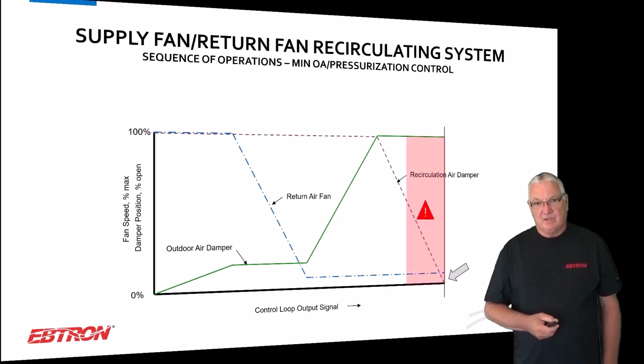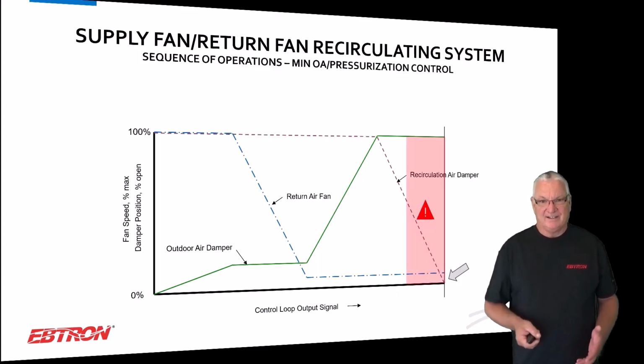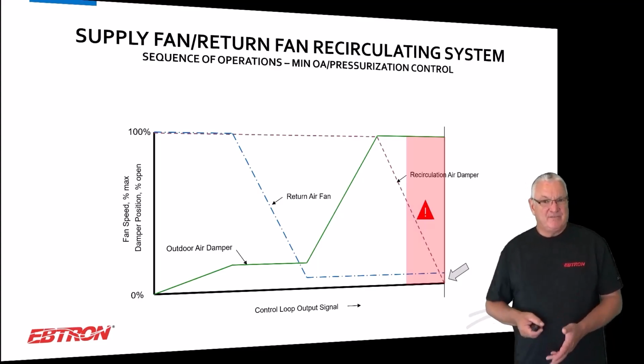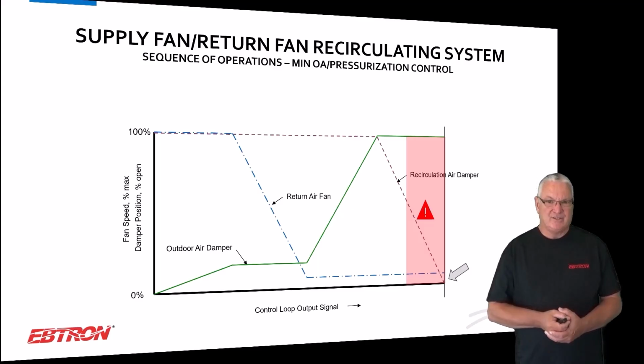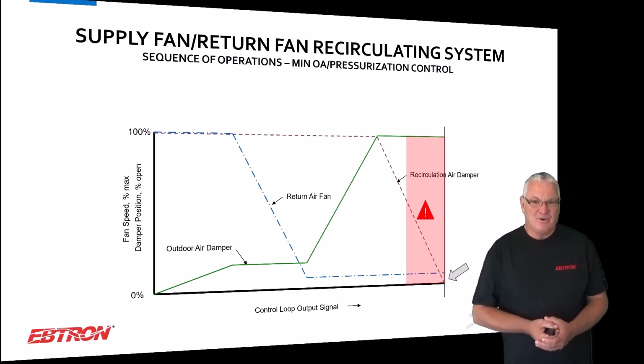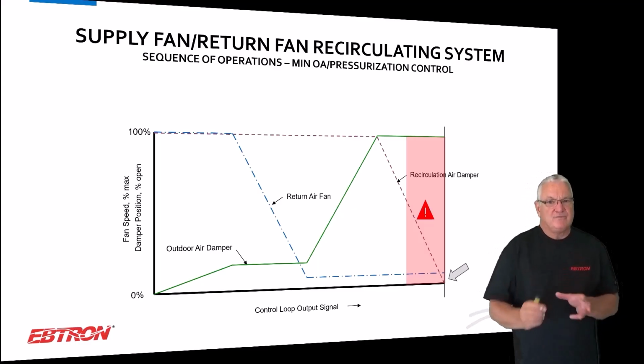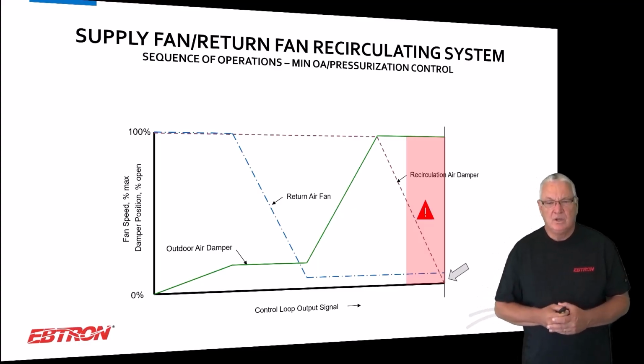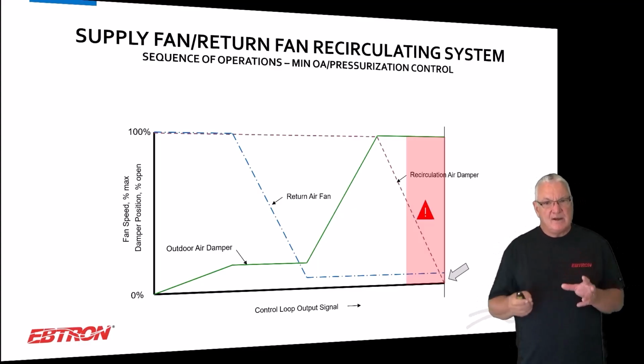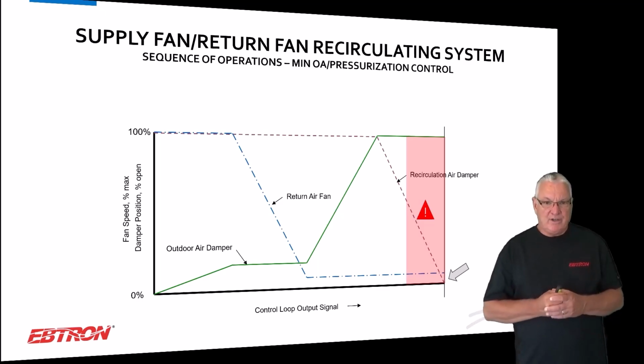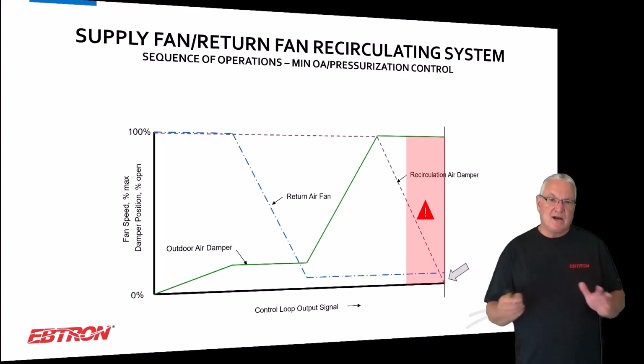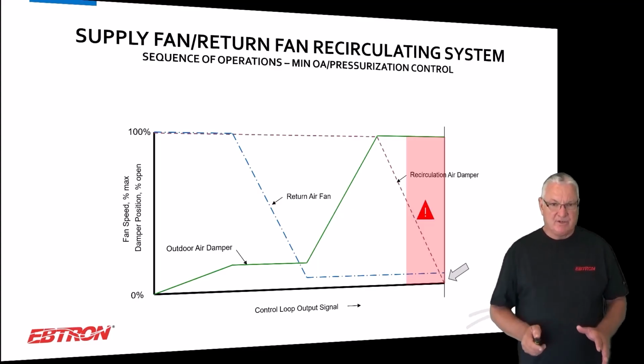So we put a little bit of a warning here. You really don't want to be there, because if you took this all the way through the full sequence, you'd have all these dampers closed and you'd blow up your air handler. So you don't want to do that, but I always like to draw the full sequence. Okay, so in this case, that would be how you control when you don't have relief at the air handler and you have a return fan. It's the most complicated strategy that I'm going to show you.